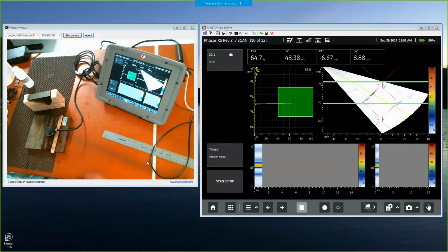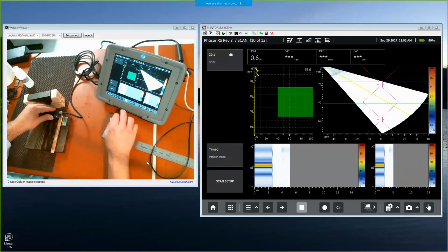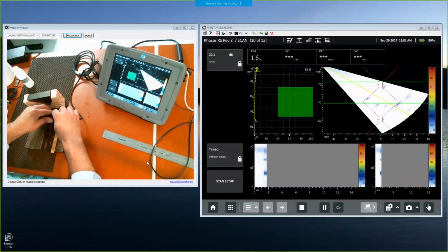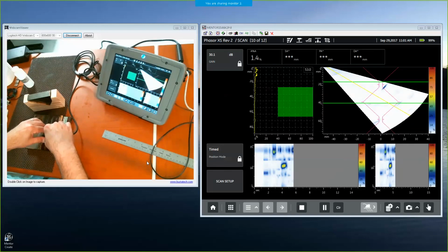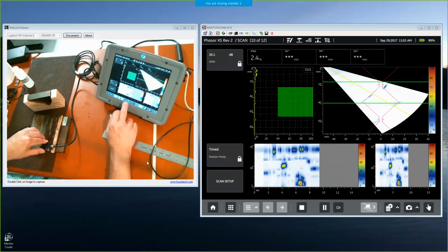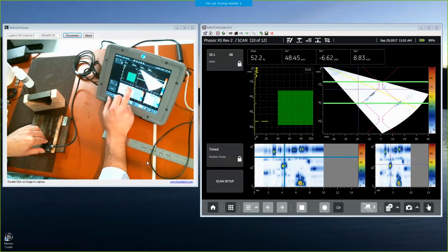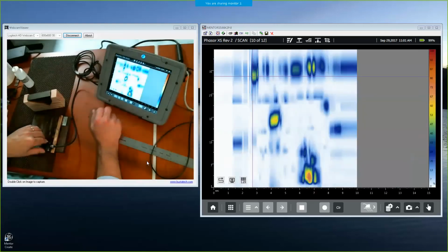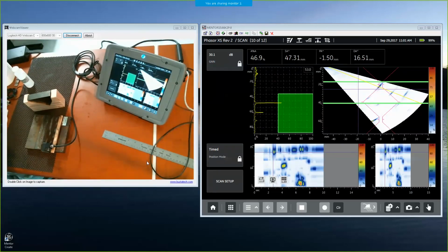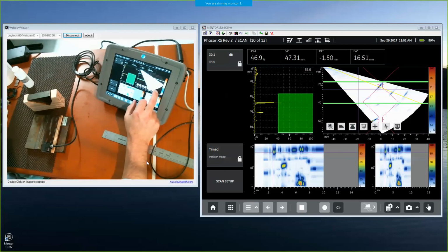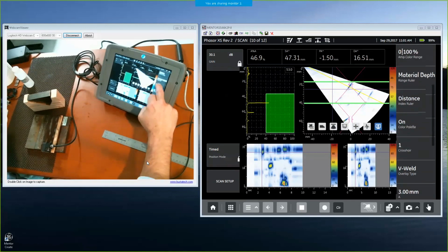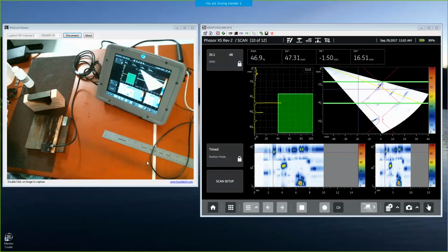Next panel is a scan panel that has the C-scan capabilities. So all of the recording features and analysis features that you were used to with the corrosion version are still here. So we can go back and review. Okay. So everything that you were accustomed to before in terms of analysis is still here. The weld overlay has been added. There are some new measurement features on the sector scan. You can turn on multiple cursors and crosshairs, and there's all sorts of measurements that can be done there. I think we'll save that maybe for another session. We'll do a session just on the analysis features.